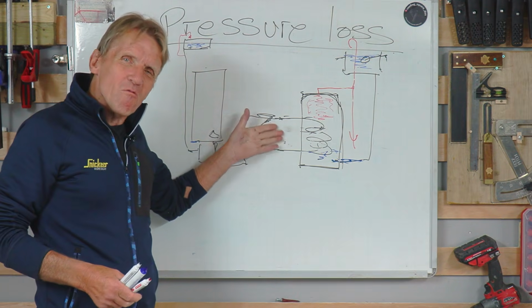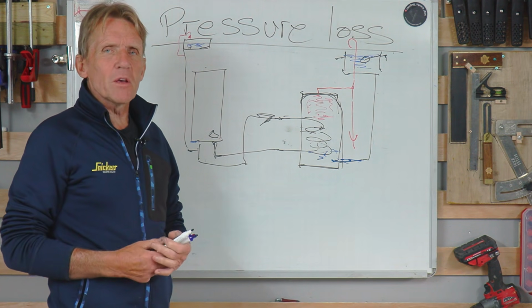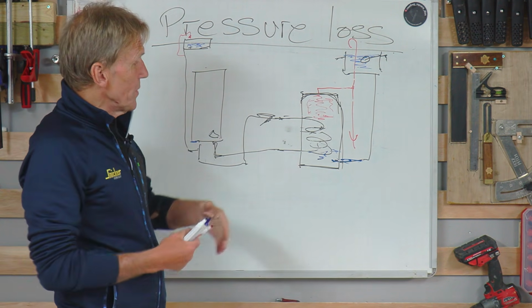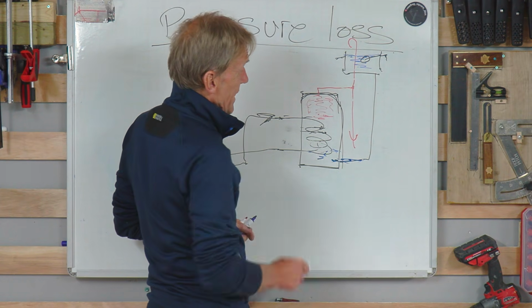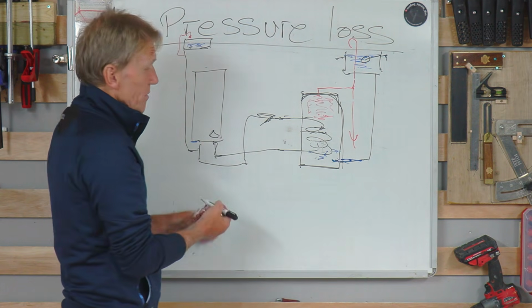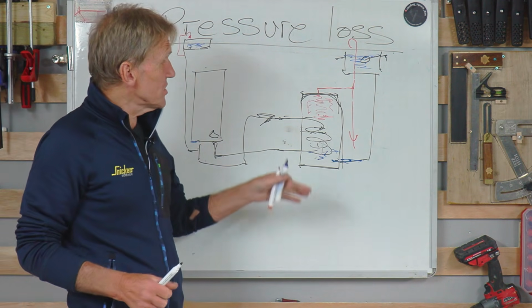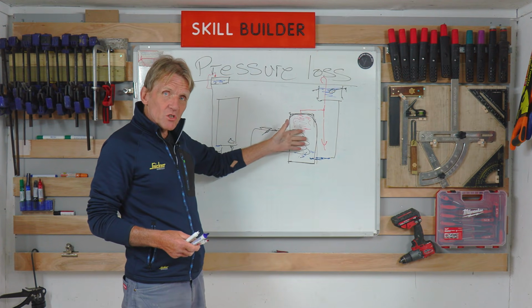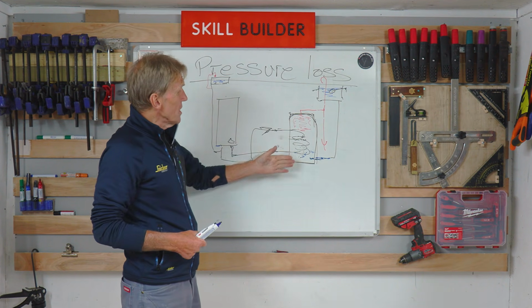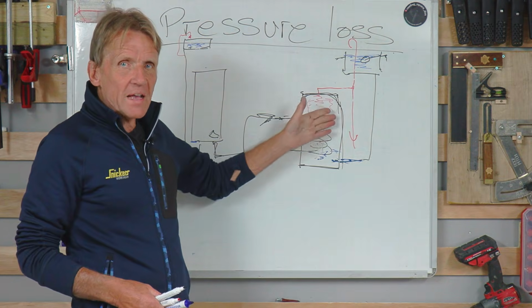So this is something we used to get reasonably often. I've probably done about 5 or 6 of these in my plumbing career. And also I had a cylinder which from day one when I fitted it was open. In other words, there was a leak in the coil there, and from the very first day I fitted it, I knew because I filled the cylinder up first and then I found there was water coming out of the central heating system, even though I hadn't filled the central heating system up. So these things do happen. That would probably be the rarest occurrence that I would see these days, because unvented cylinders tend not to leak internally in any appreciable time, but it does happen. And if all else fails, that's something you need to look at.